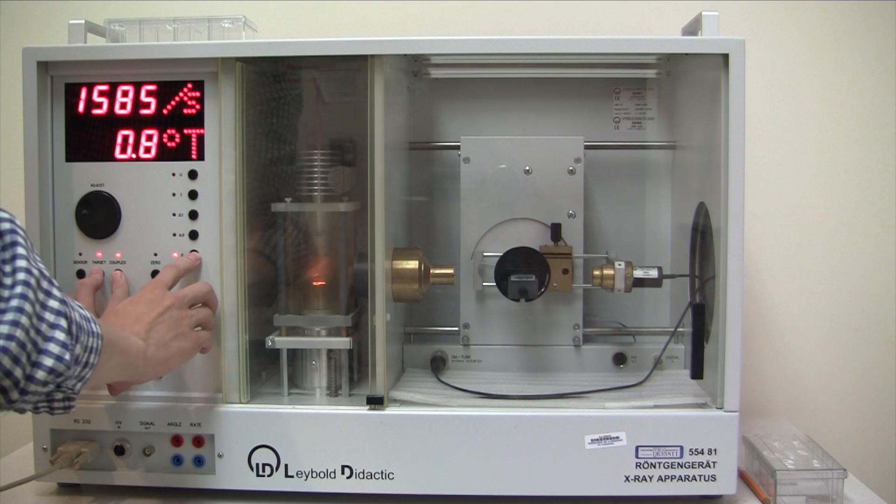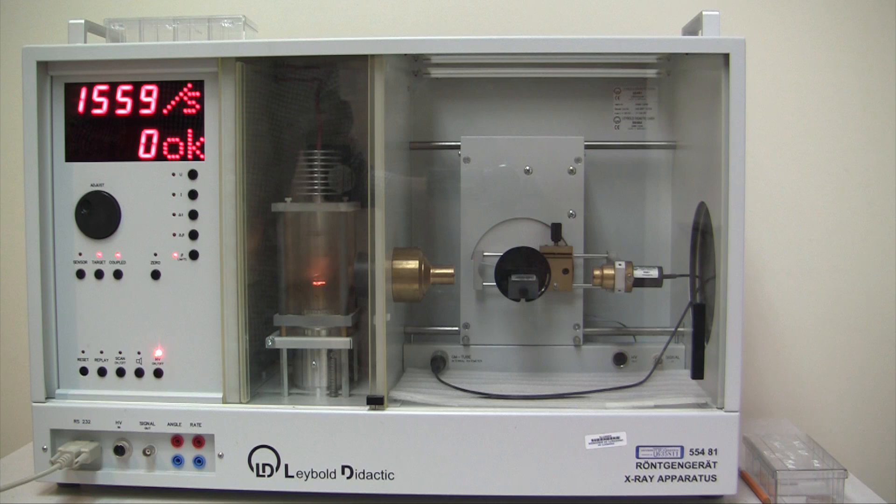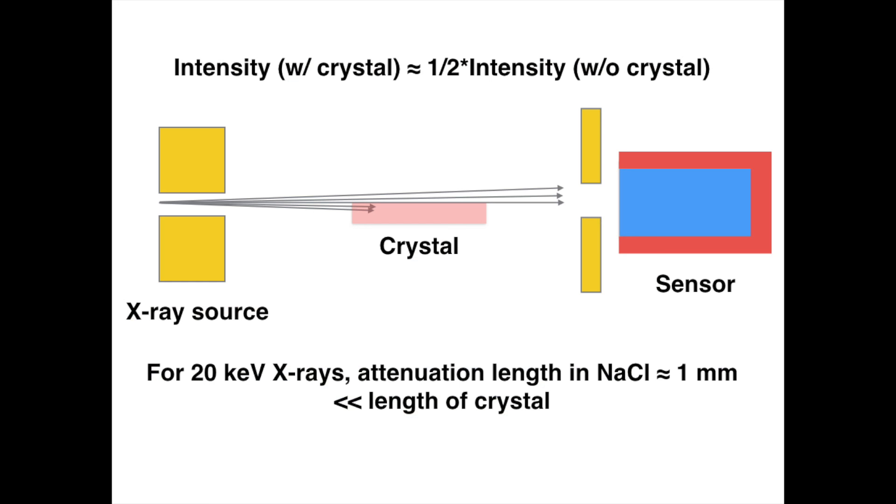Simultaneously depress the target, coupled, and the beta limits buttons. This should initiate the recalibration sequence and move the goniometer to 0 position. Consider when the source, the crystal and the sensor are perfectly aligned with each other. With the crystal in place, most of the X-rays that hit the crystal cannot pass through, due to the fact that the attenuation length of the X-ray is much smaller than the length of the crystal. Therefore, compared to the case without the crystal, the intensity received by the sensor reduces to about half.